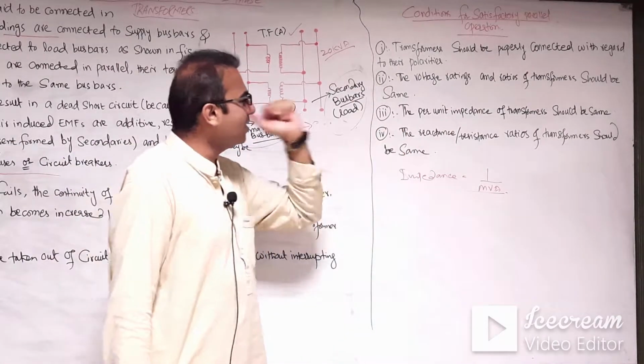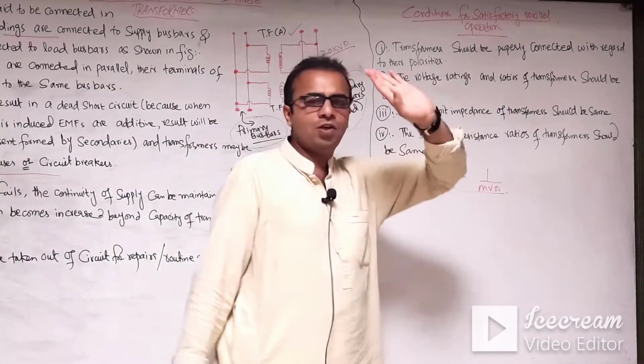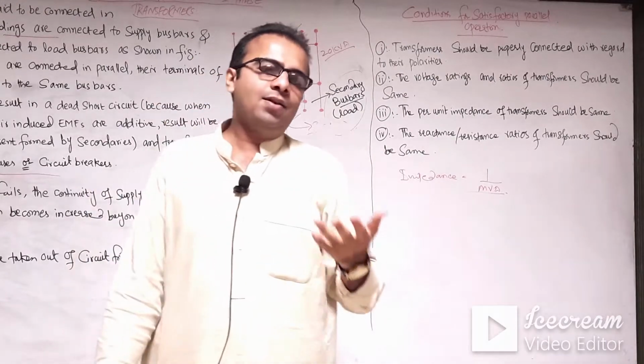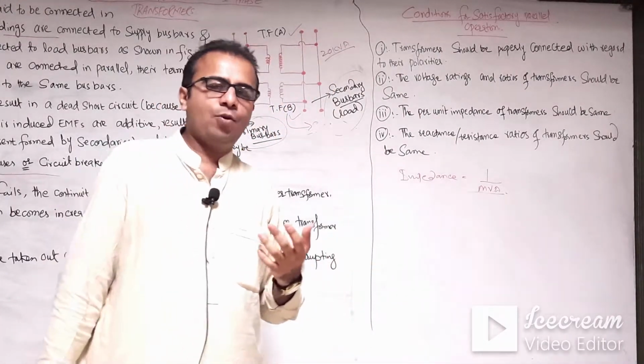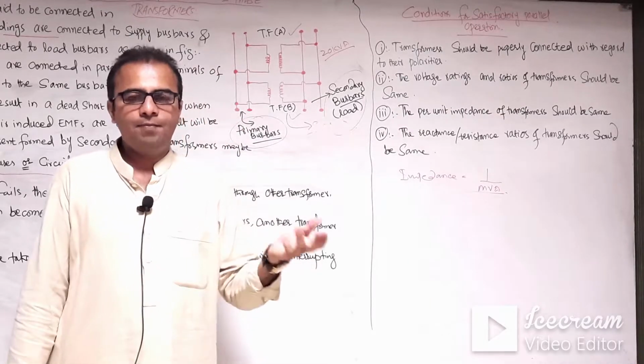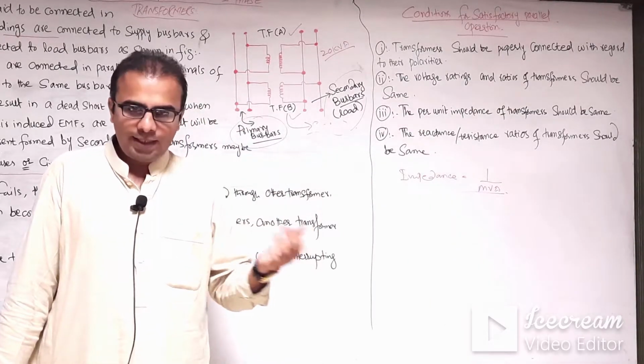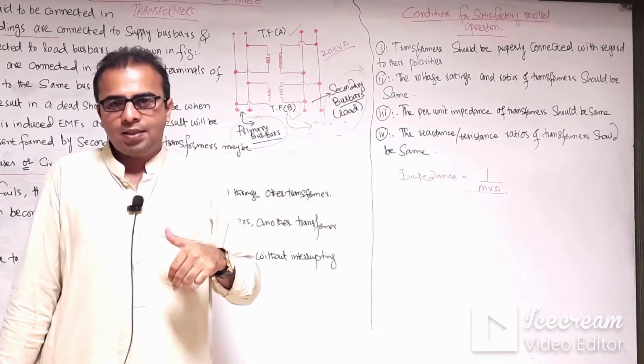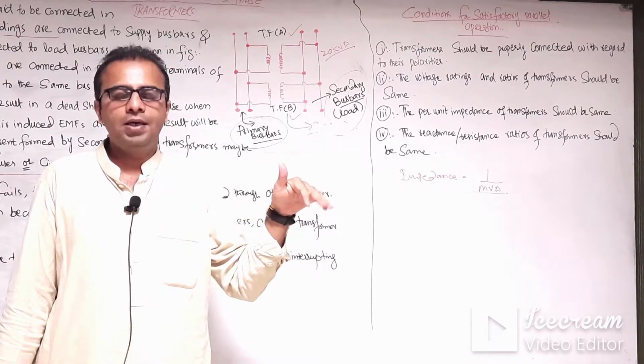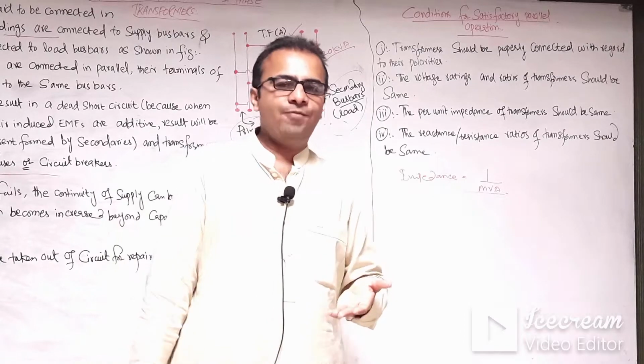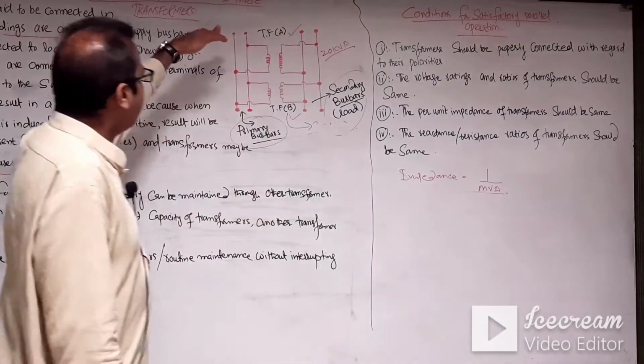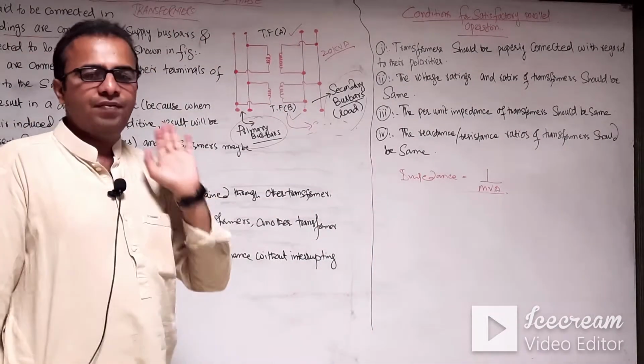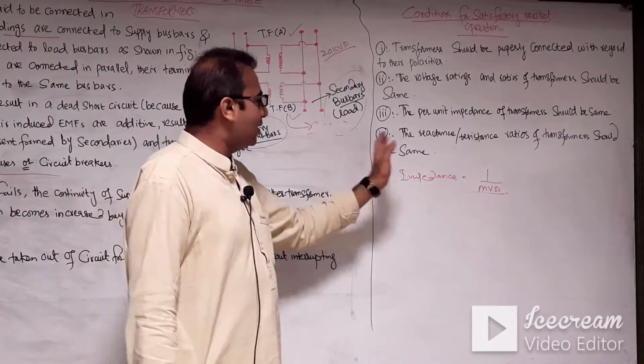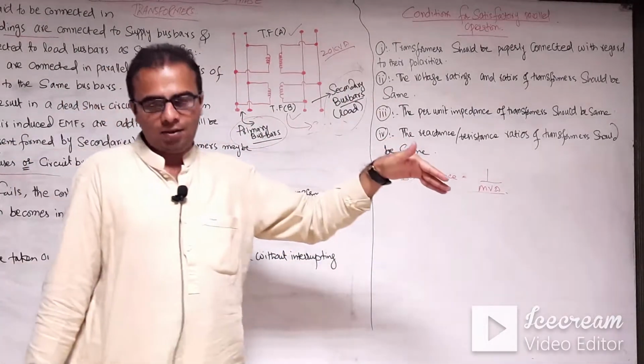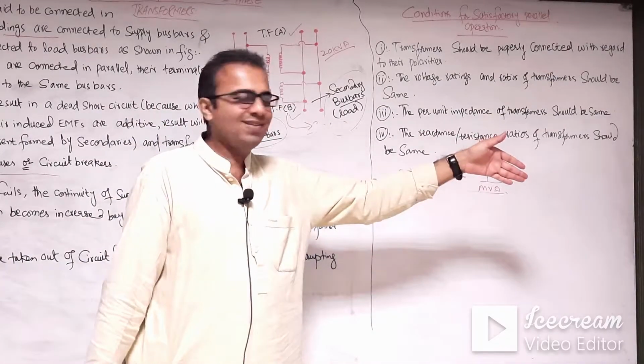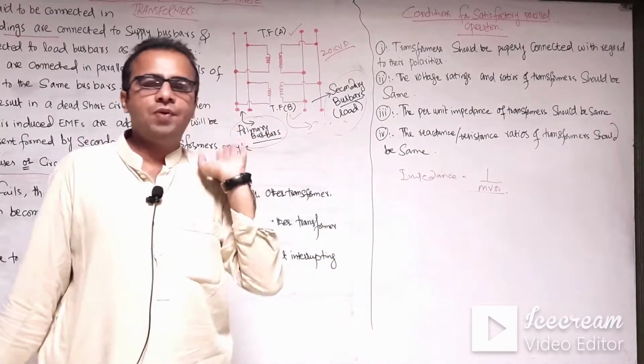Number three is that the per unit impedance of the transformers should be the same. The currents of the transformers are proportional to their MVA ratings, the apparent power or kVA ratings. So the impedance of the transformer is inversely proportional to the MVA rating, and the impedance of both transformers, like transformer A and B, should be the same. And fourth is that the reactance over resistance, X by R ratio, of both transformers should be the same.